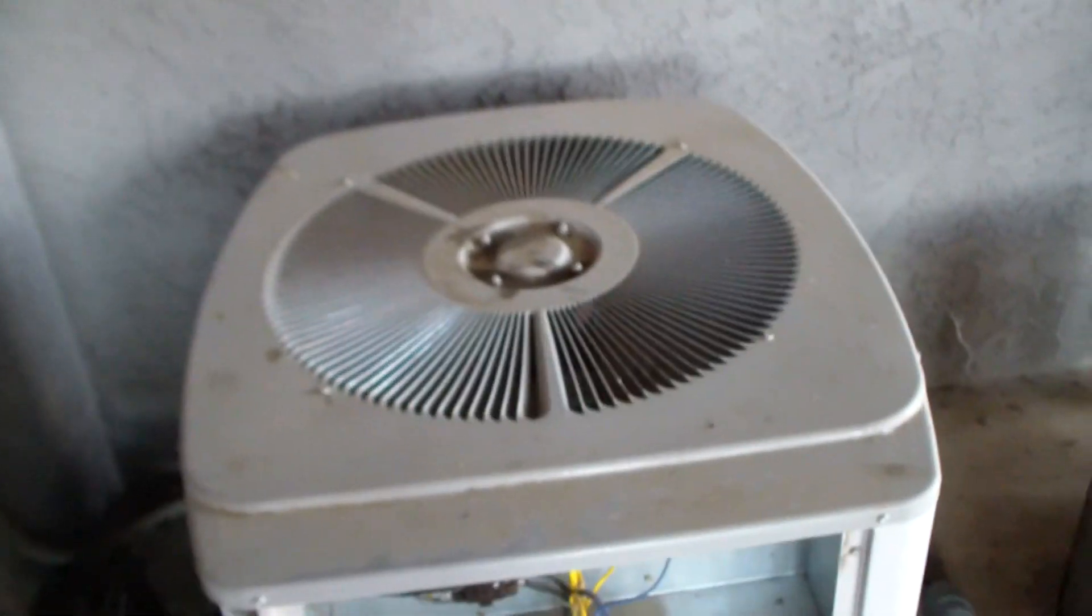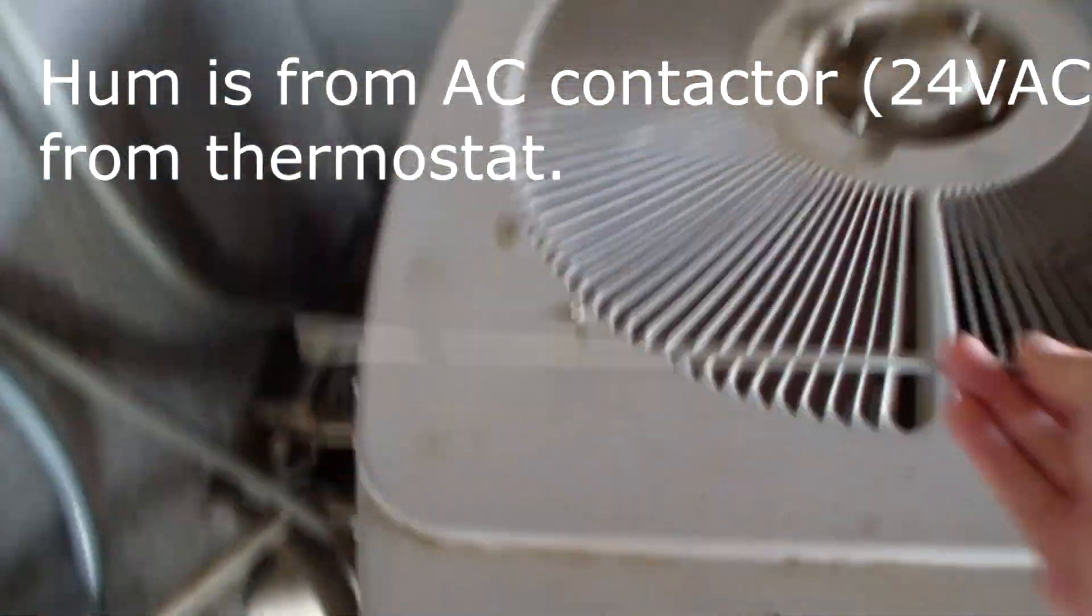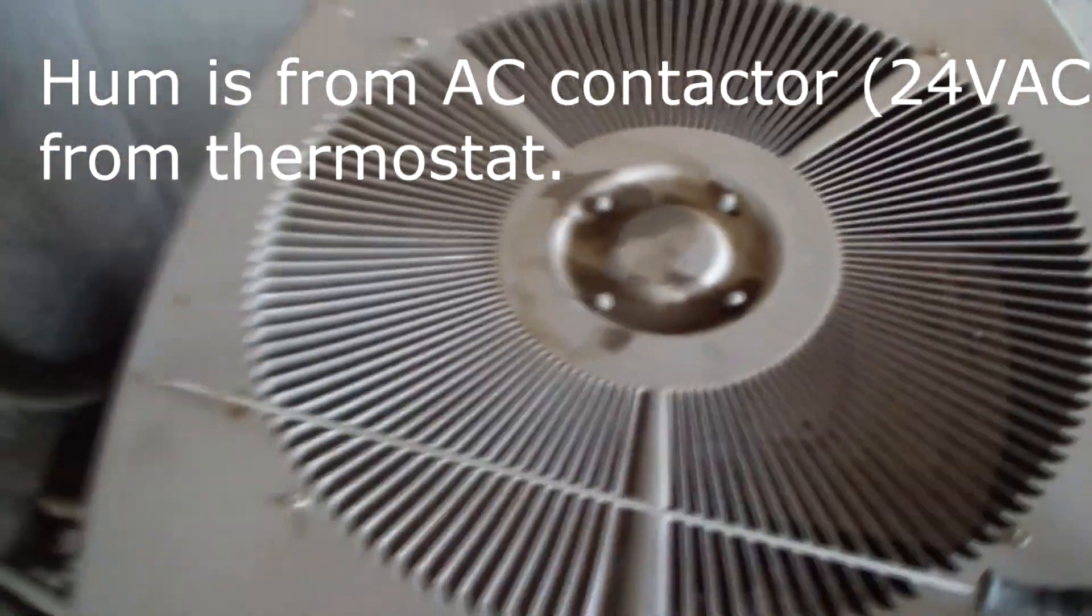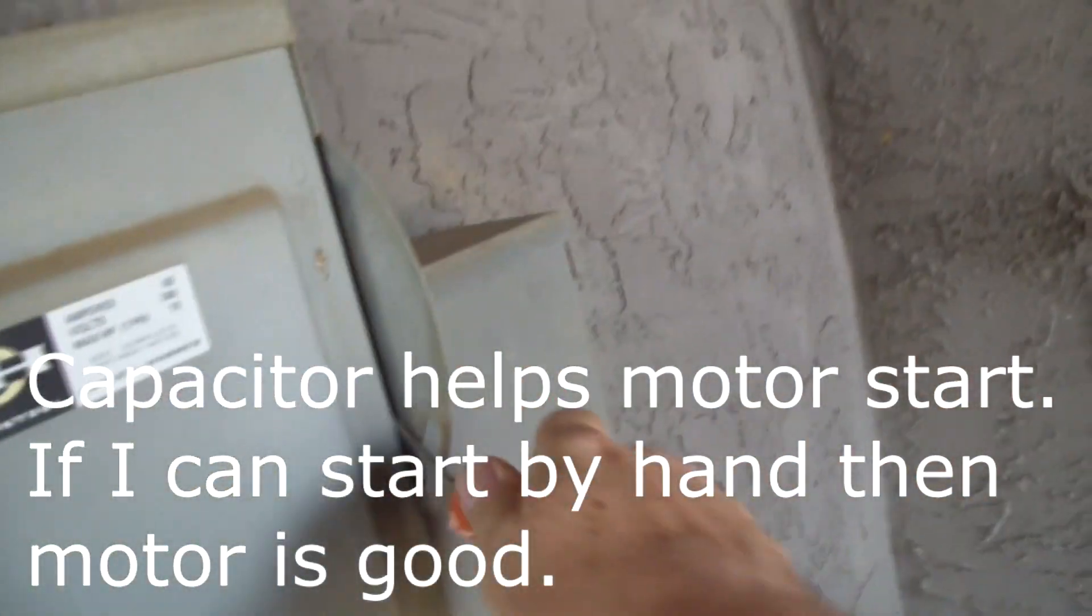Okay, I'm going to try a little experiment to see if the motor works with a little jump. I'm going to take a little screwdriver and spin the motor by hand, but first, you can hear the thing humming. I got the air conditioner on, and now we'll flip the breaker and see what happens.